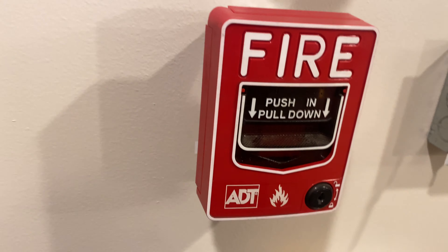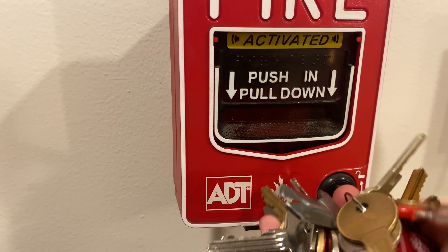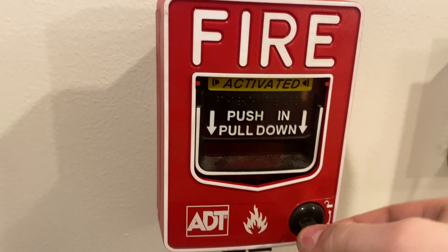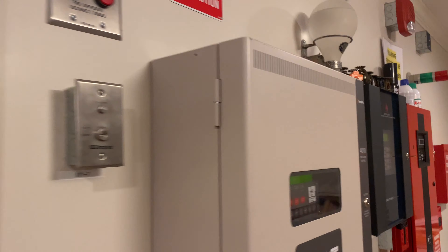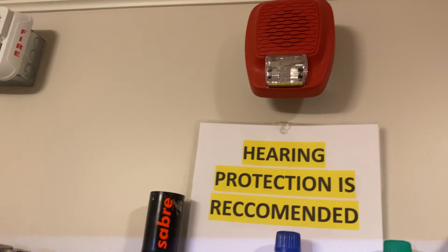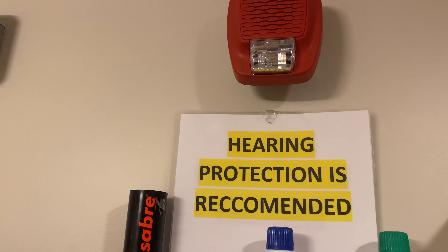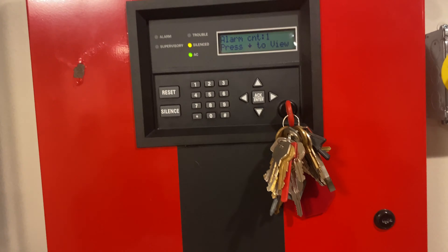Panels are reset. Let's do the ADT BG-12L. Pulling that now. I'm sure you've probably heard that Wheelock strobe is kind of raspy — that seems to be a common thing. I know a couple of other people who have the same device who also say it's kind of raspy and rattly, no matter what power source you put on it. I think that's just the nature of the alarm.